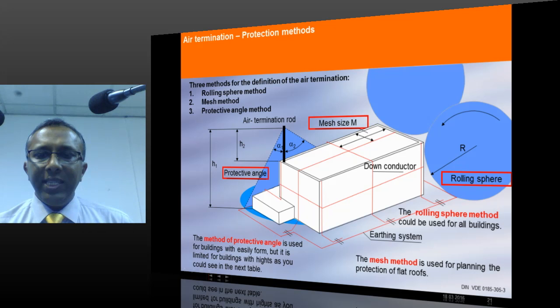For example, in this particular case, you can see if we roll this sphere across the building, from here it starts. This place it won't touch, it is a protected place. From here onwards, it will touch the building, throughout the surface it will touch, and maybe again something like this. What it means is, for this particular value and this particular building, from this point where I am keeping the mouse up to this point, there is a chance of a direct lightning strike. Rolling sphere will not give any protection. It will only give an indication of where lightning can strike. So to protect that area, either we need a rod, or a mesh, or a catenary wire. So three ways are explained here.